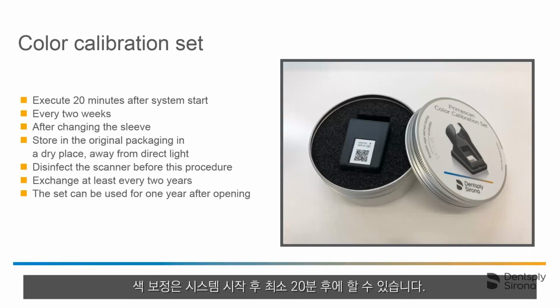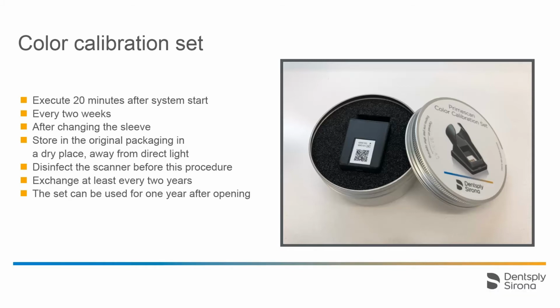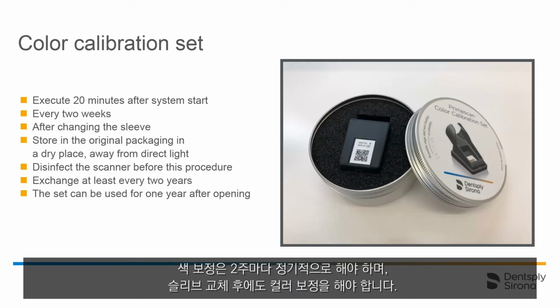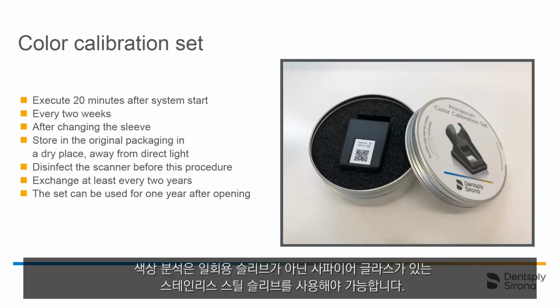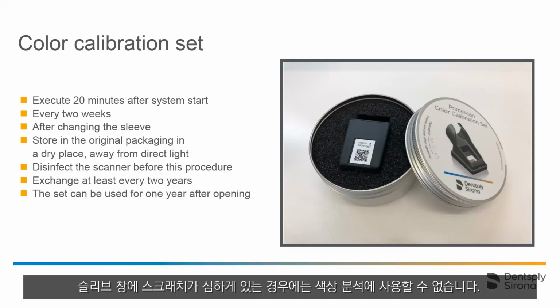A color calibration may only be performed at least 20 minutes after system start. Color calibration must be done on a regular basis. The recommended time is every 2 weeks. A color calibration should also be performed after changing a sleeve. A color analysis can only be carried out using the stainless steel sleeve with sapphire glass, not with a disposable sleeve. A heavily scratched sleeve window can also no longer be used for a color analysis.